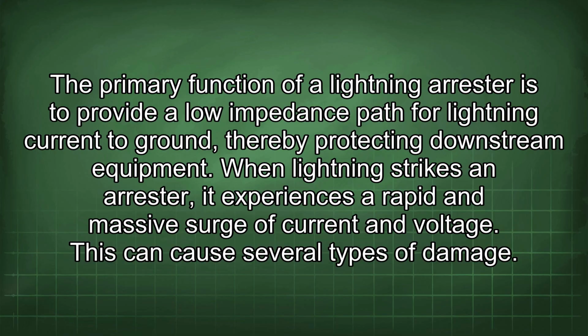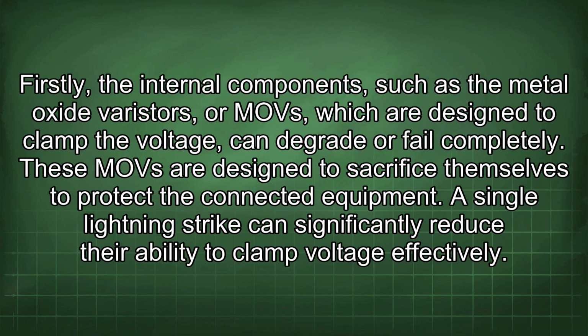When lightning strikes an arrestor, it experiences a rapid and massive surge of current and voltage. This can cause several types of damage. Firstly, the internal components, such as the metal oxide varistors or MOVs, which are designed to clamp the voltage, can degrade or fail completely. These MOVs are designed to sacrifice themselves to protect the connected equipment. A single lightning strike can significantly reduce their ability to clamp voltage effectively.